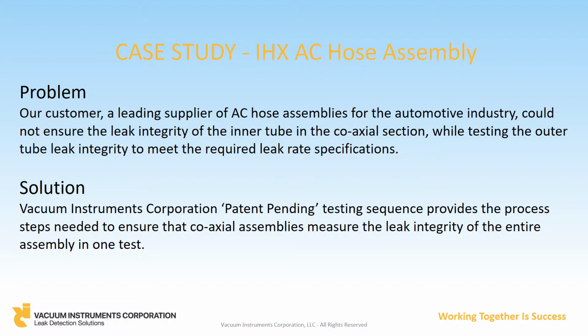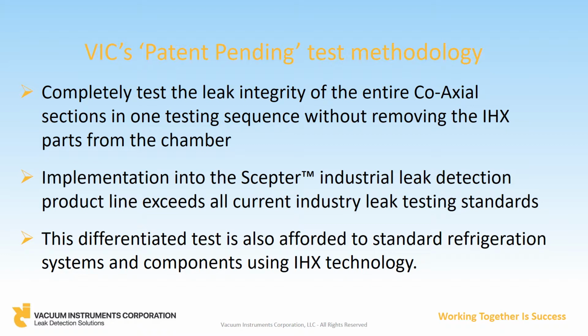We developed a hard vacuum leak test system that not only tests the inner and outer tubes separately, but also measures the leak integrity of the entire assembly in one test. VIC's patent-pending test methodology was implemented in the Scepter, VIC's hard vacuum system for thermal applications. The Scepter allows the parts to be loaded into the fixture assembly, which is in the chamber, and evacuates and charges first one circuit of the IHX part independent of the second circuit while performing a leak test. Then it isolates and tests the second circuit, thus allowing us to completely test the leak integrity of the entire coaxial section in one complete testing sequence without ever having to remove the part from the vacuum chamber.